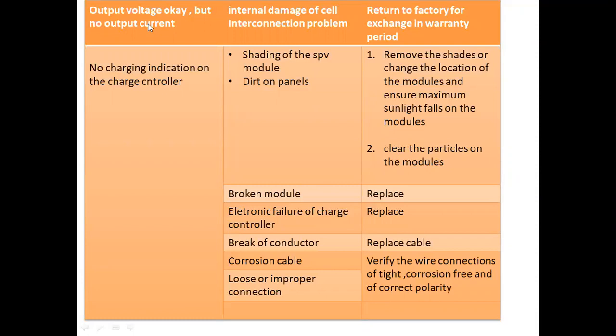Next, output voltage is okay but no output current. This means there is internal damage of the cell line — solar cells have internal series connections, and if those connections break, the cell line is damaged. This is internal damage of the solar module. We need to repair it at the company's servicing point under manufacturing warranty, or replace the module.